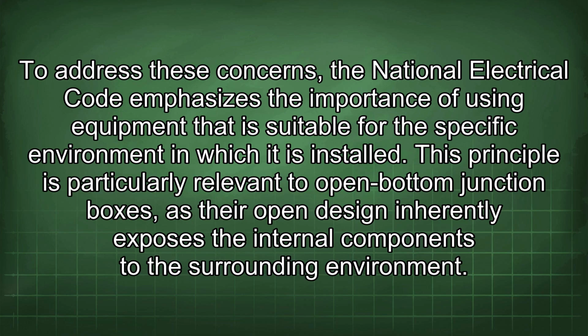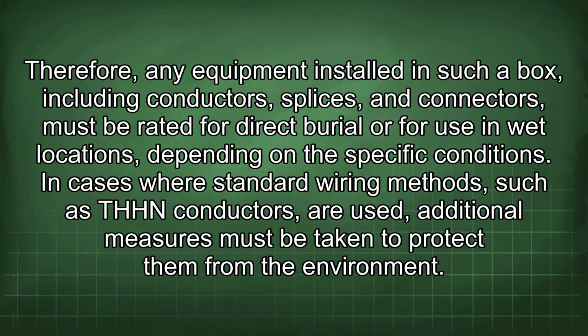To address these concerns, the National Electrical Code emphasizes the importance of using equipment that is suitable for the specific environment in which it is installed. This principle is particularly relevant to open bottom junction boxes, as their open design inherently exposes the internal components to the surrounding environment. Therefore, any equipment installed in such a box, including conductors, splices, and connectors, must be rated for direct burial or for use in wet locations, depending on the specific conditions.